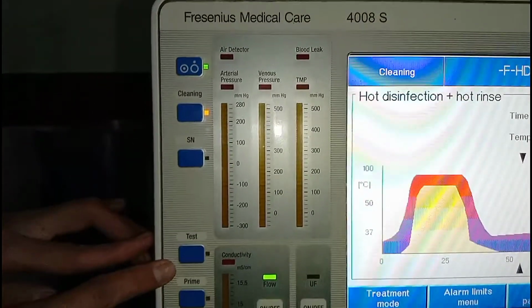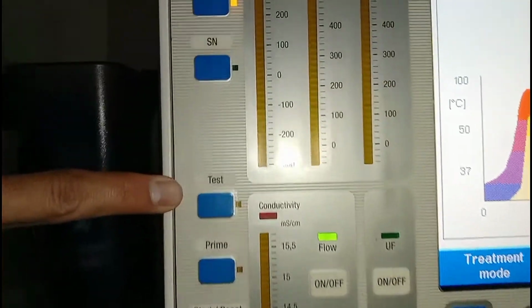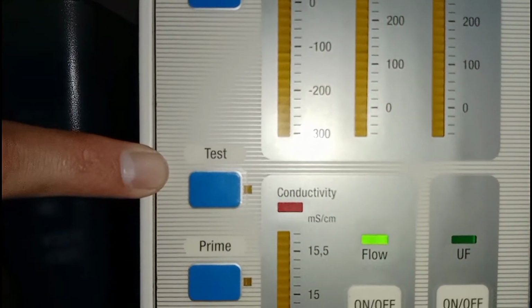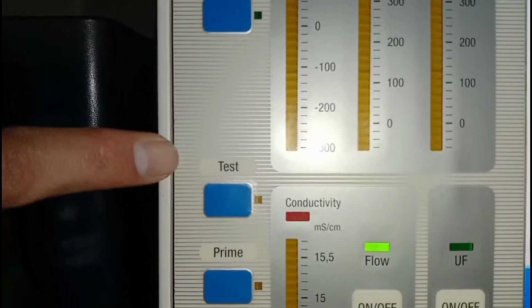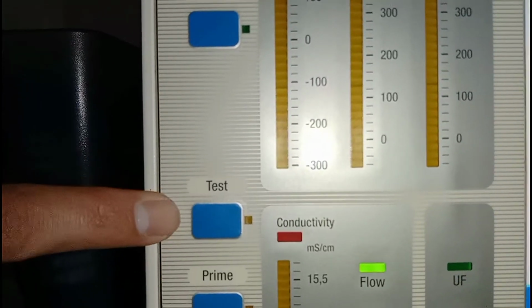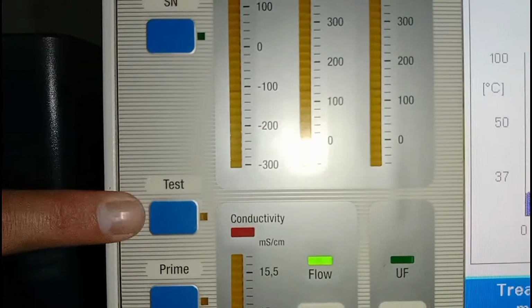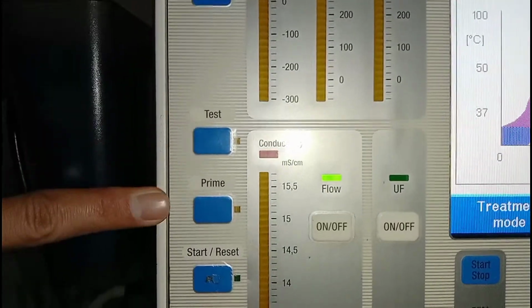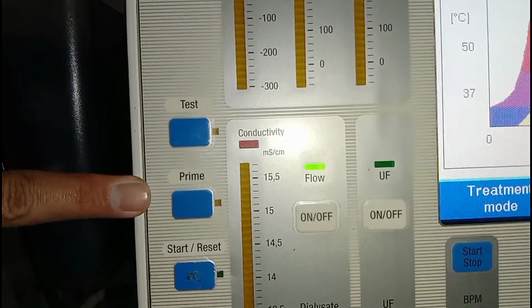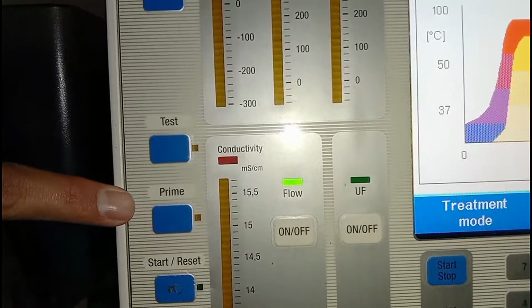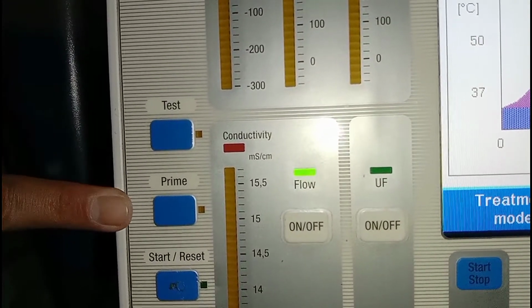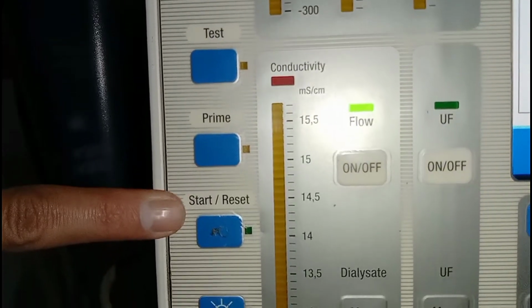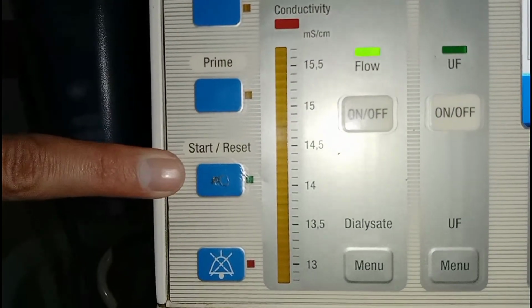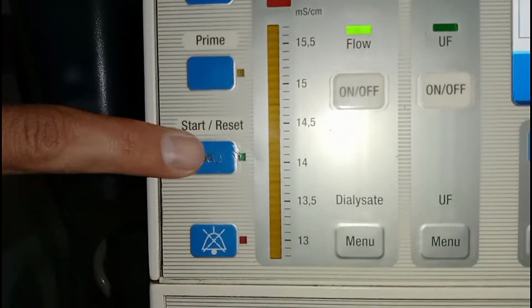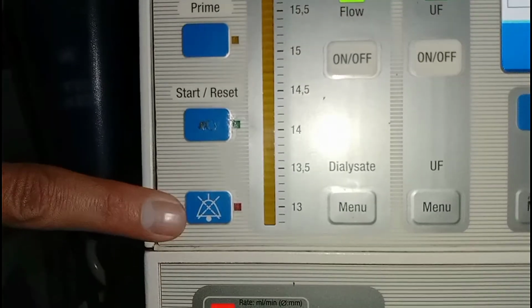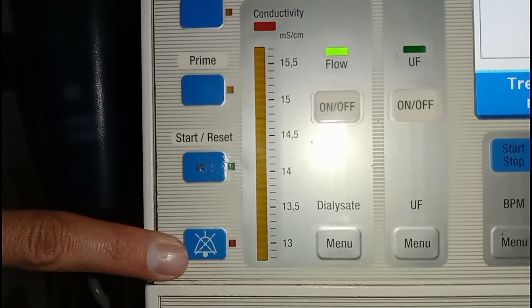Below this there is an option of test. If you want to put your machine through different tests, that is conductivity, venous pressure, and temperature test, the machine can be put on test by this button. Below the test there is the prime button. You can prime the hemodialysis circuit, the extracorporeal circuit, with the help of this button. Below this is the start or reset button. You can reset the machine with this button. Below start or reset there is the mute option. You can mute the alarm with this button.